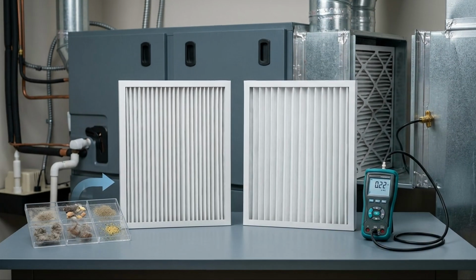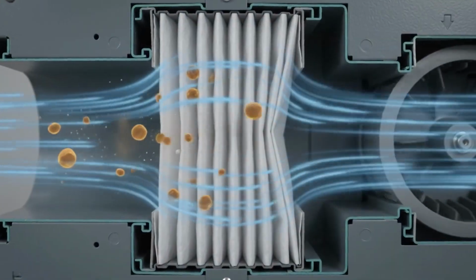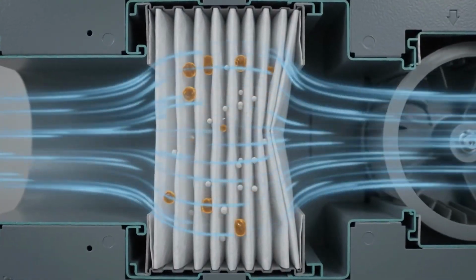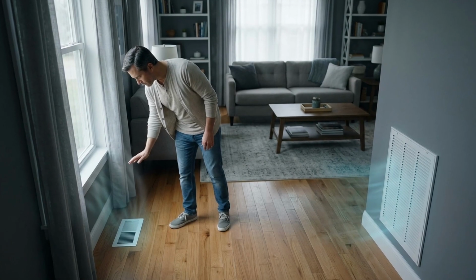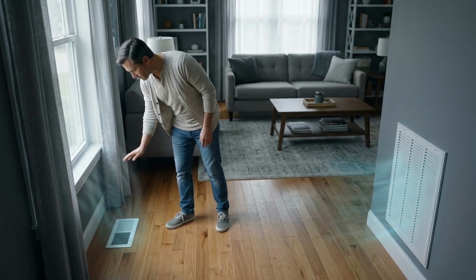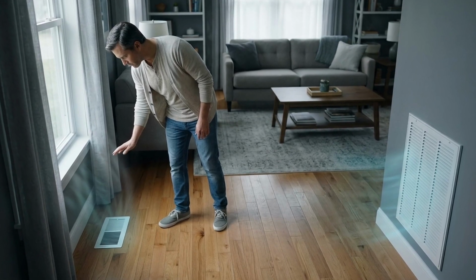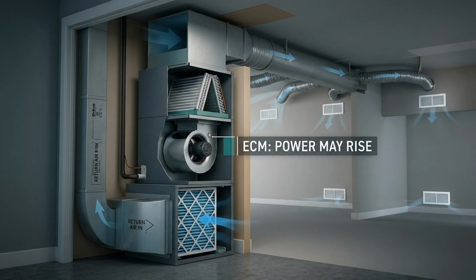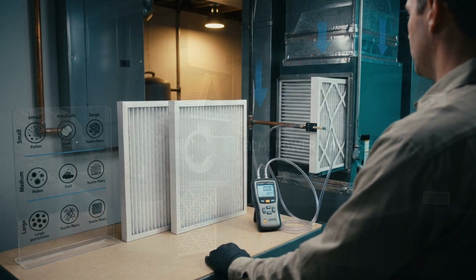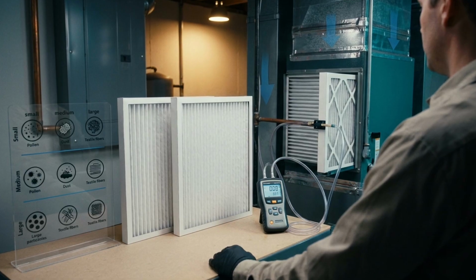You replace an ordinary HVAC filter with one that captures smaller particles. A day later, the filter looks like an upgrade. But one room feels slower to cool, and the air at a supply register seems weaker. That does not prove the new filter is wrong, and it does not prove the equipment is failing. It tells you that two separate questions have been mixed together.